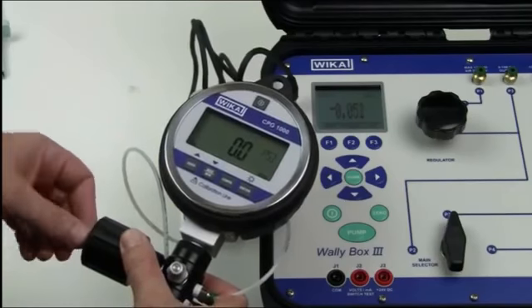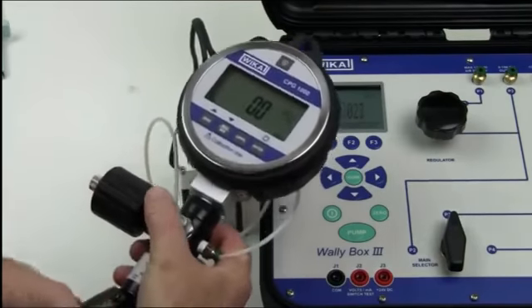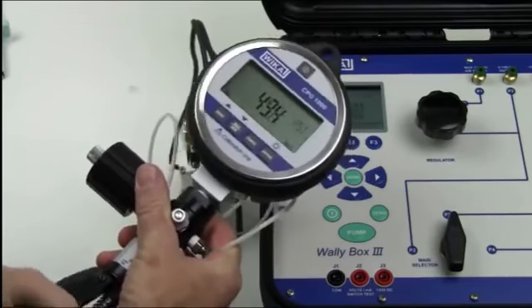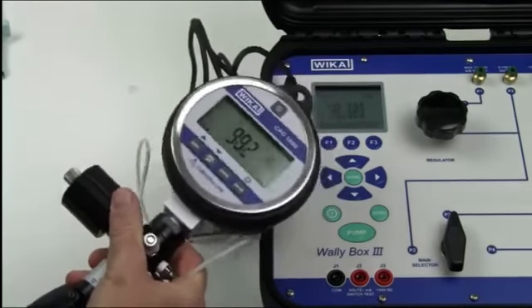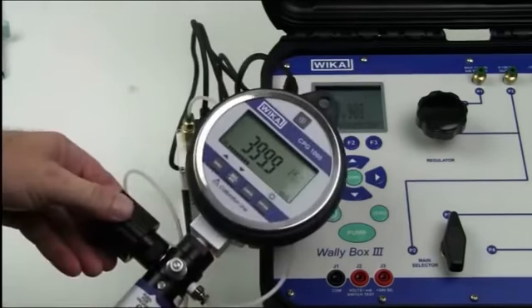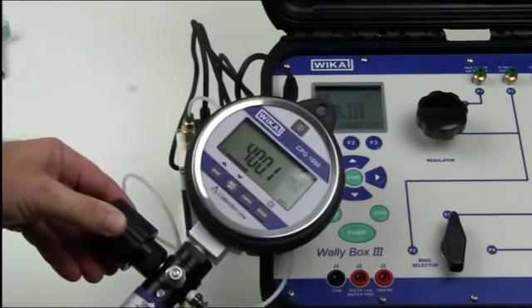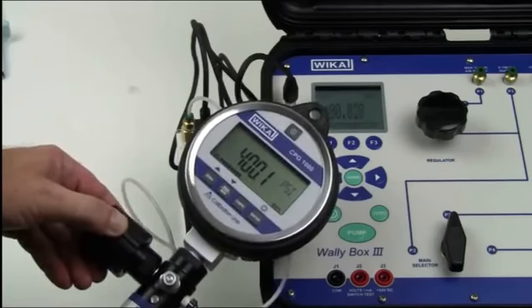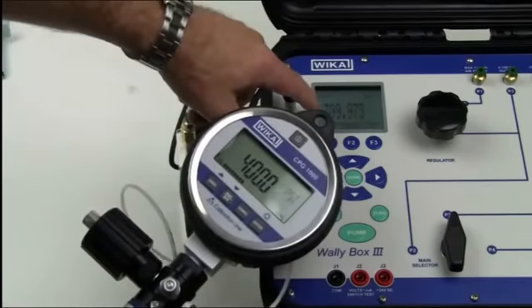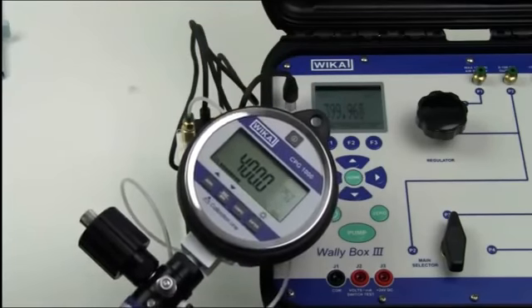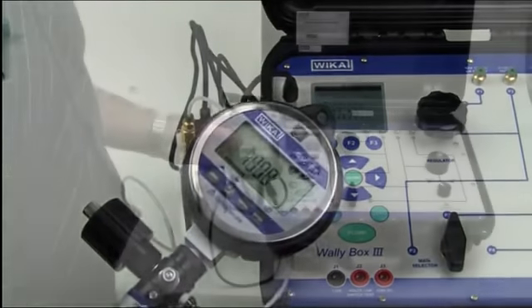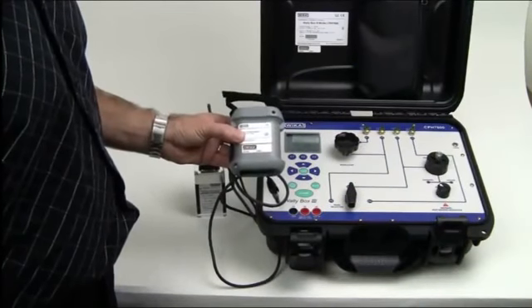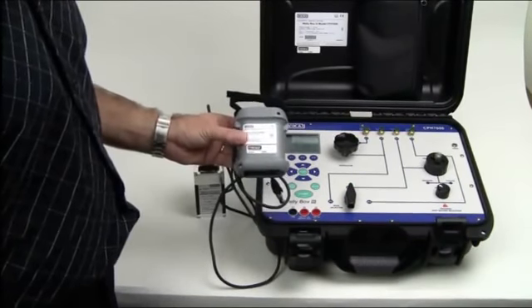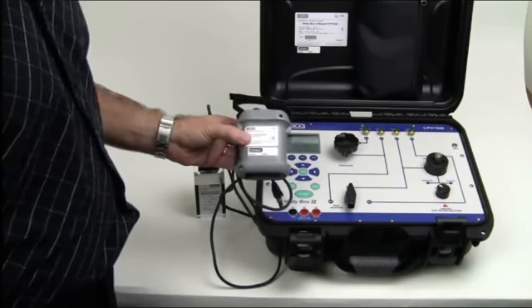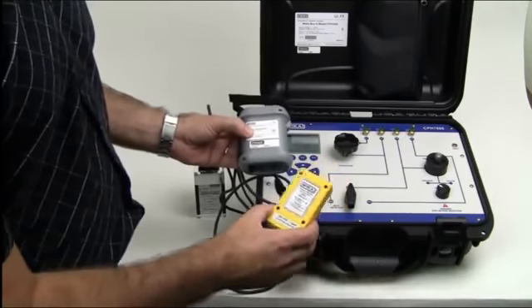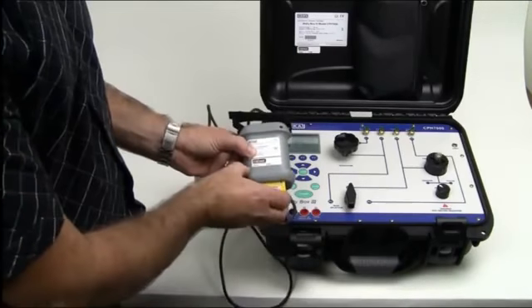Let's now get our gauge under test up to 400 psi. We now set the adjustment on the gauge to 400, and then we're able to determine the exact reading from the transducer displayed on the Wally box. To extend your Wally box for higher pressures, you can also purchase a pressure module adapter which is compatible with a whole range of CPT 6600 pressure transducers.